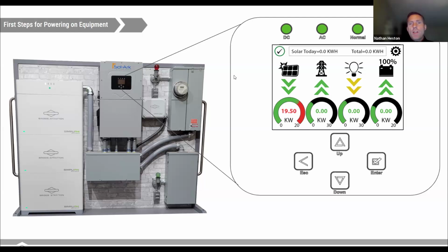When you're first turning on the Sol-Ark, the Sol-Ark itself has an AC power supply, so there's a 200 amp service panel with a 200 amp disconnect here. That power comes in through the utility port on the inverter and then goes out of the inverter to the load center in this example. When you first turn on the inverter, you'll see a screen that appears like this. There's a gear icon there. It is a touch screen, and you have the ability to change settings using the up and down, enter, and back or escape buttons.